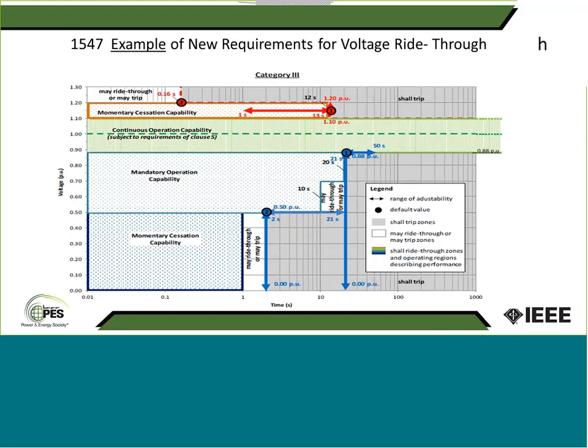Yes, that's a really good question. We are currently working with NERC on that. Yes, there's a bit of conflict there. Having inverters not produce current may not be helpful when it comes to grid stability. You're momentarily losing that inverter, right? So when it comes to supporting the grid, you definitely need power generation, current generation. So the answer, again, is yes. We're working closely with NERC to see what needs to be done on the PRC-024 standard.